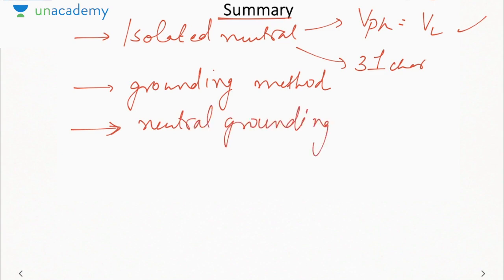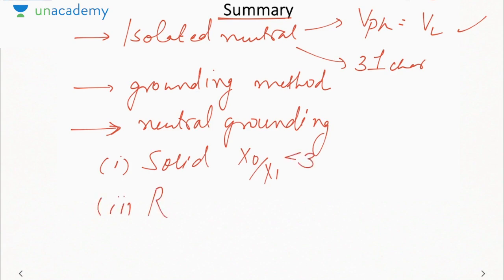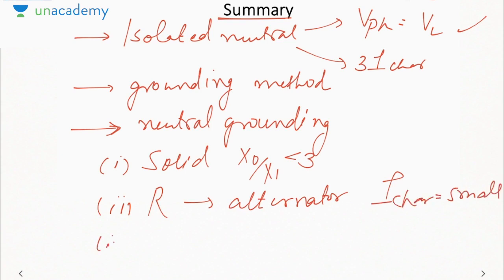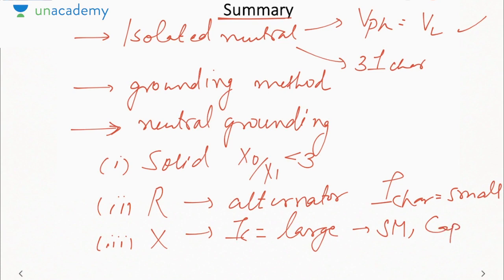We first saw solid grounding, which will be used if x0 by x1 is less than 3. Then we saw resistance grounding, which is used in alternators to improve the stability, and it is used where I charging is small. Then we saw reactance grounding. It is used where IC is large, which will be the case when we will be using synchronous motor or capacitor bank.